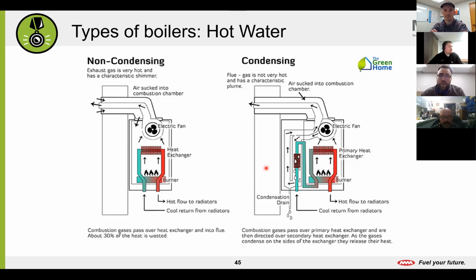Boilers in general have two categories. We have non-condensing, or what we call standard efficiency, and then condensing, which is high efficiency, right? So non-condensing boilers are usually anywhere between 70 and 85% efficient, right? So for every dollar you spend, you get 70 to 85 cents of heating out of it. Condensing boilers, I believe the highest I've seen is 98.5%. I believe that was the latest statistic. But yeah, 98.5 cents for every dollar you spend on heating actually gives you heating into your water.